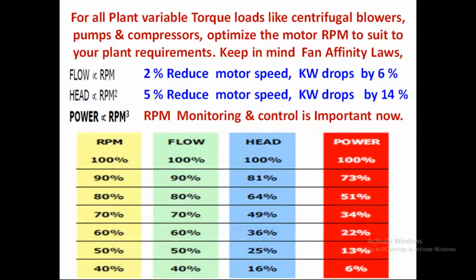At a 2% reduction of motor speed, subject to the optimum static pressure and the flow that is required at the load end, 6% power savings is possible, and at a 5% reduction in the motor speed, straight away 14% savings is possible. So VFD coupled with resizing of the pulleys: VFD alone can achieve some amount of savings. Let us say 70% of the savings is achieved. The balance 30% of savings can be achieved by resizing the pulleys and belts, so totally 100% of the savings is possible. I mean to say 100% of that 30% can be achieved by VFD and pulley resizing, whereas with only VFD, out of that 30%, only 20% is possible.